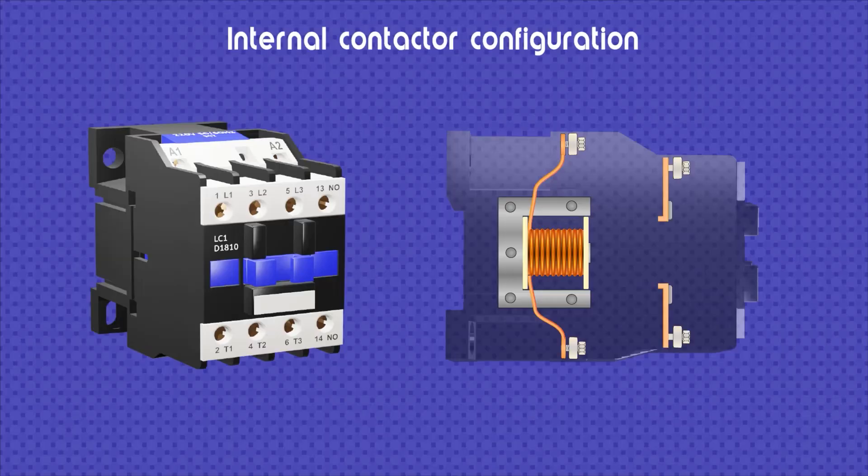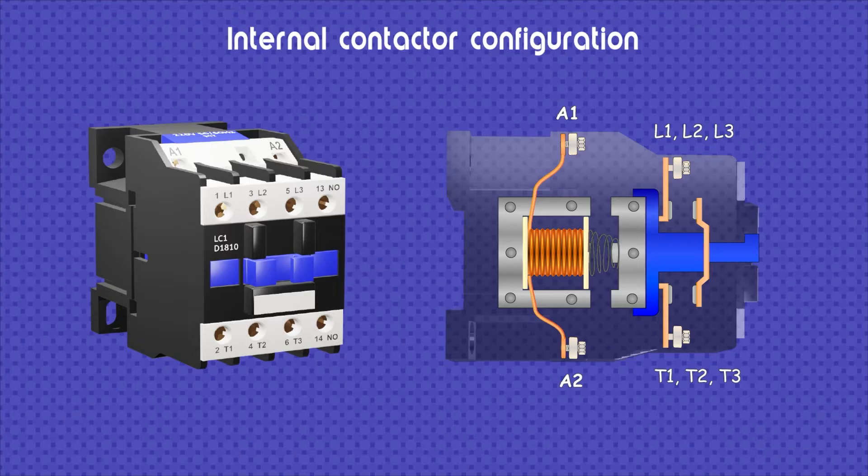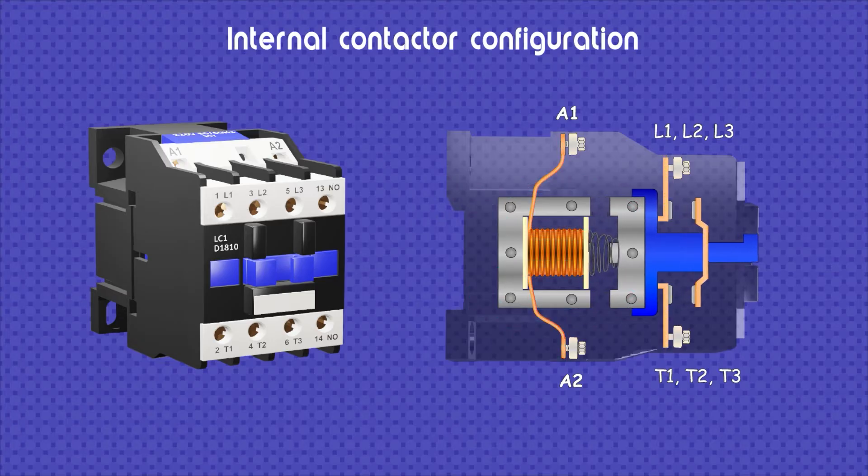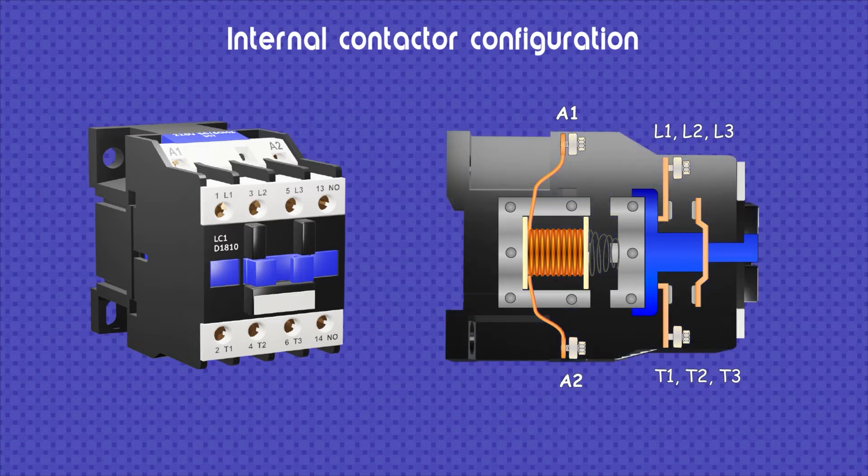Here is an animation of what happens inside the contactor. When the coil is energized, it generates an electromagnetic field that attracts the moving part of the contactor. In this way, the main and auxiliary contacts close and allow current to pass to the load. If the coil is de-energized, then the spring located between the moving part and the coil pushes the moving part to its default place.